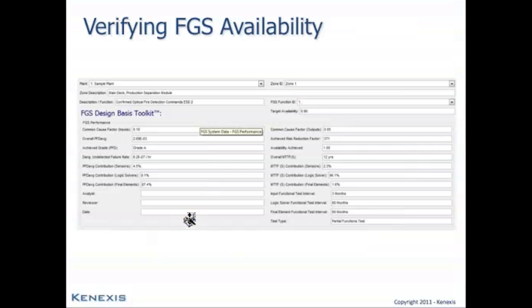The actual verification is typically done by using some sort of probability of failure on demand modeling tool. The excerpt that is shown here is from the Kenexis FGS Design Basis Toolkit, whose calculations are primarily based on the simplified equations contained in ISA Technical Report 84.00.02, which is the premier source of calculation equations for performing safety availability and probability of failure on demand calculations.